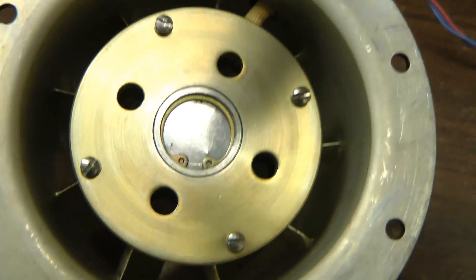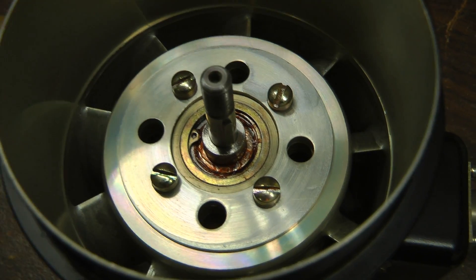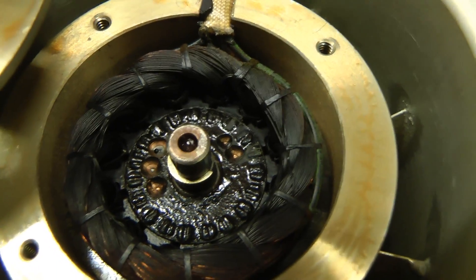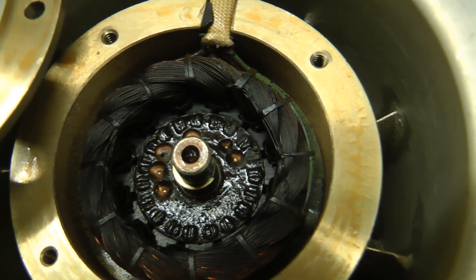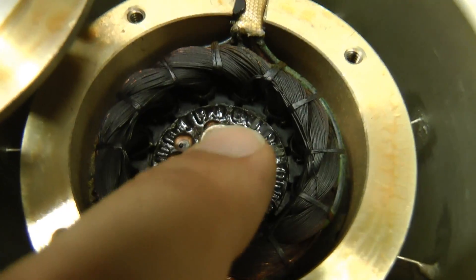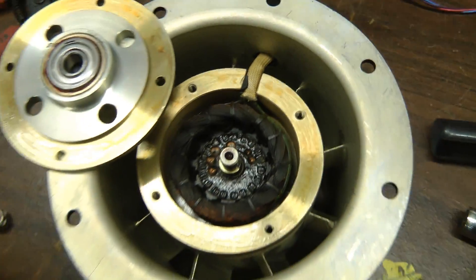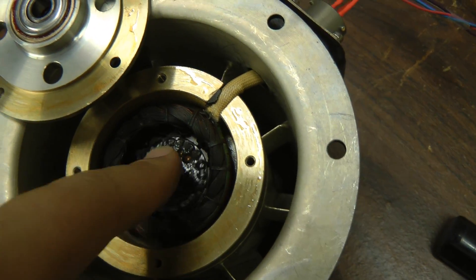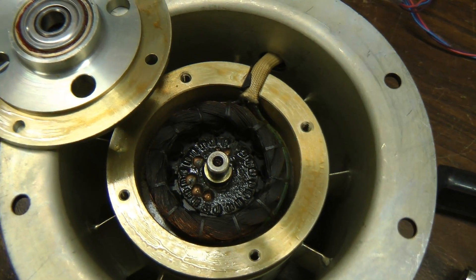Yeah, let's see if we can pull at least the back end off the motor and see the windings and maybe the rotor. Curious if the rotor on these high frequency motors looks any different from a 60 Hertz one. That came off really easily. You know, the rotor looks somewhat different than the one from a normal motor. There's drill balancing holes. You can see the rotor conductors are made of copper rather than the normal aluminum. Also the clearances are very tight. There's very little play there. Of course, pretty high quality bearings. Pretty thin wire on the motor as well. But yeah, it's really small when you think about it - just for scale - and how much power this tiny little motor puts out, probably at least 500 watts. Just demonstrating how much better 400 Hertz is for keeping things very small.